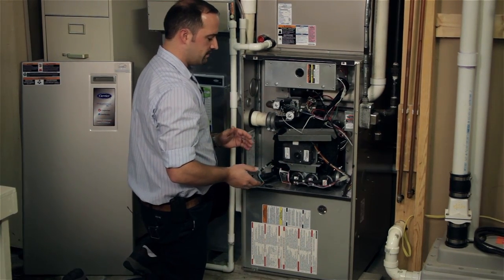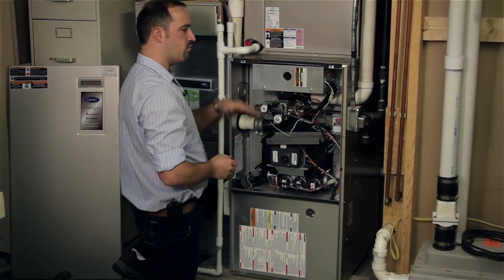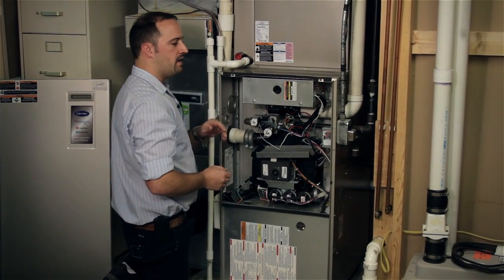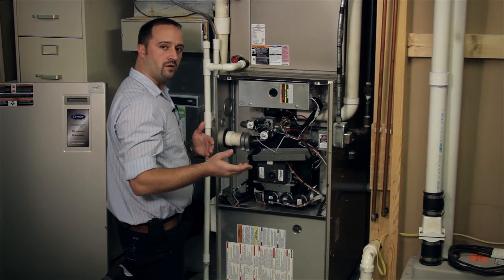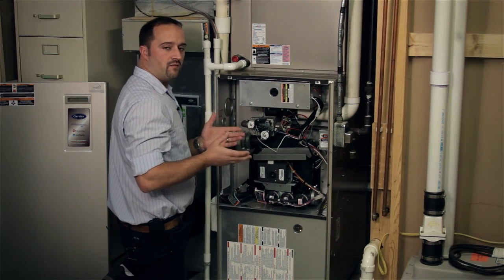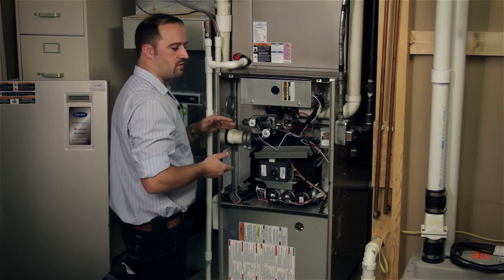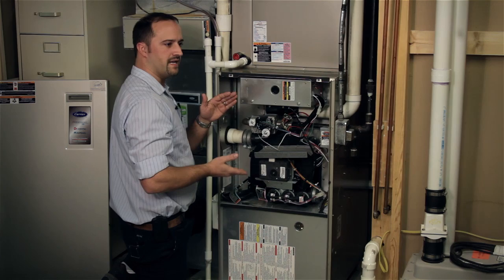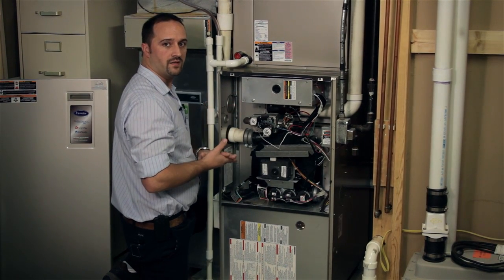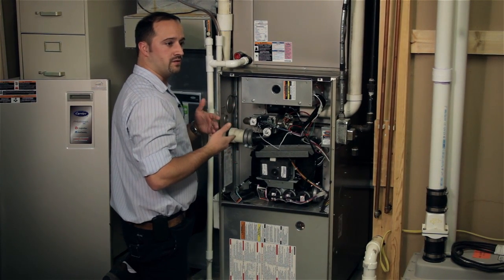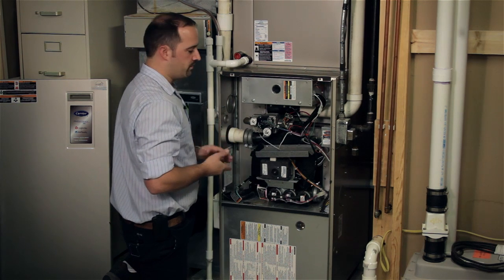After he gets that all checked out, he's going to measure how warm the air is going through the furnace. Every furnace, like I said before, they always revolve around how much air is moving through them. So there's a certain range that temperature has to be when the air goes through that furnace. So he's going to measure that to make sure, is it running the way it's supposed to?